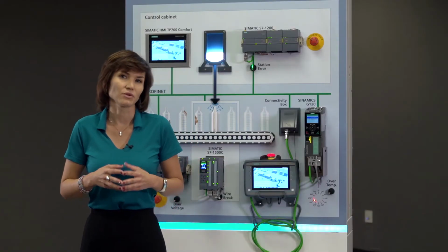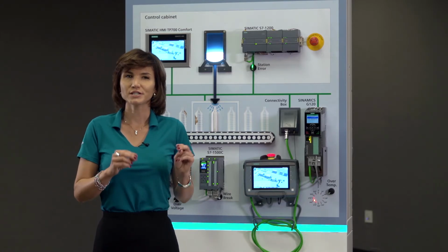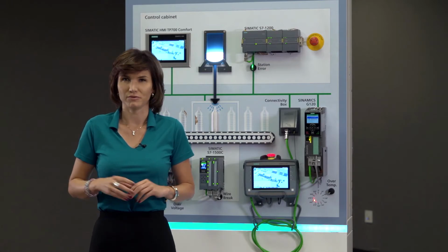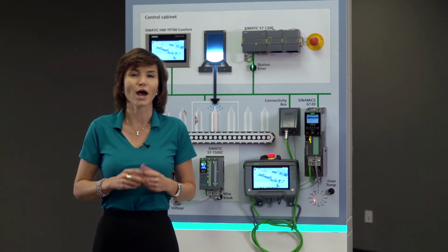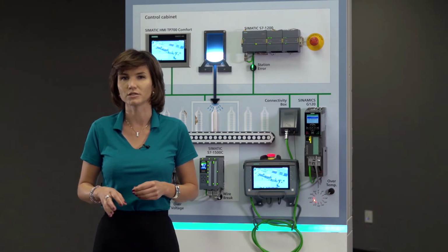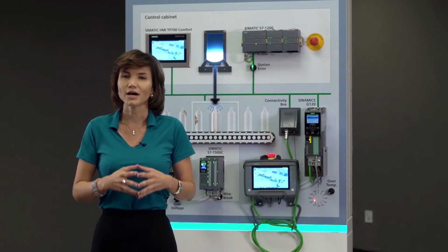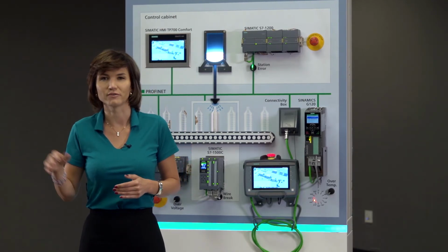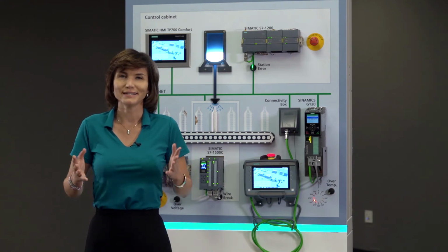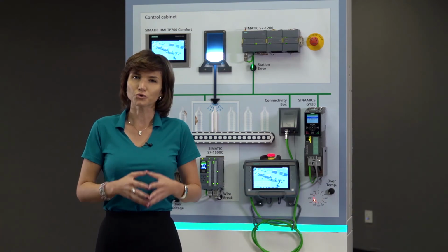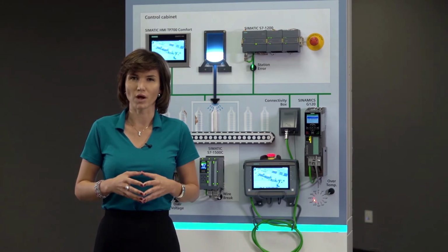Another fancy thing I would like to mention is iDevice. iDevice stands for intelligent CPU as an I/O device. With this functionality, Profinet not only permits I/O communication with subordinate devices as an I/O controller, but also I/O communication with other central or higher level controllers as an I/O device. iDevice basically enables very fast controller-to-controller communication, which happens simultaneously on one common bus.